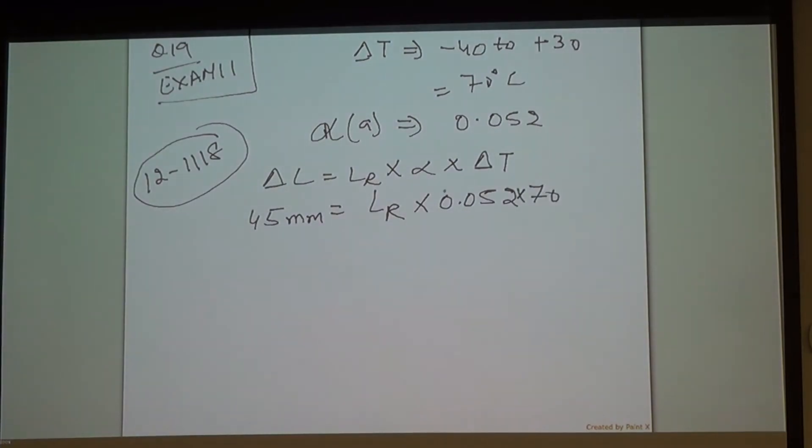45 mm. The rule that I'm following is 12-1118. Up to 45 mm of expansion, I do not need to install expansion joint. 45 mm equals length of the raceway not given, alpha 0.052, delta T 70 degrees. I'm going to ask Farid to multiply these two numbers for me. Multiply 0.052 and 70. Tell me what you got. 3.64.